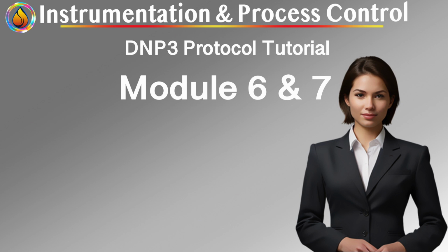6.5 Data concentrator architectures. Concentration function. A data concentrator collects data from multiple field devices and exposes it as a unified dataset to a master. Key characteristics: aggregation of many outstations, local buffering and event handling, single upstream communication endpoint. Protocol homogeneity and conversion. Data concentrators may communicate DNP3 downstream and upstream, translate between DNP3 and non-DNP3 protocols, normalize proprietary data into DNP3 objects. In all cases, the upstream master interacts using standard DNP3 semantics.